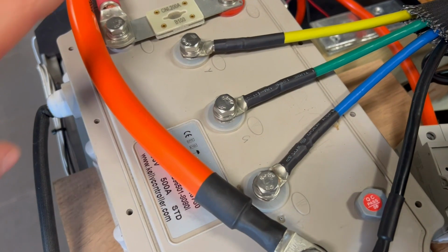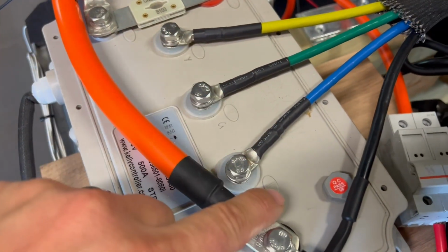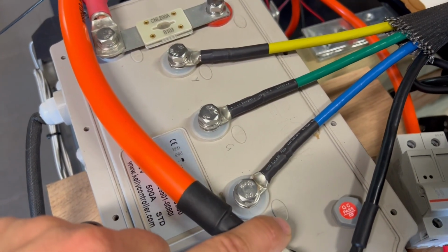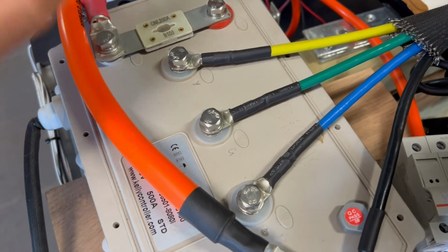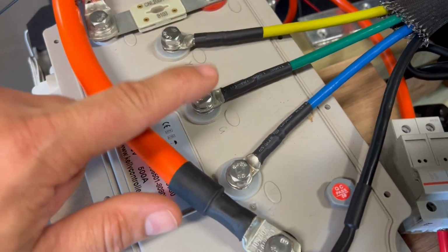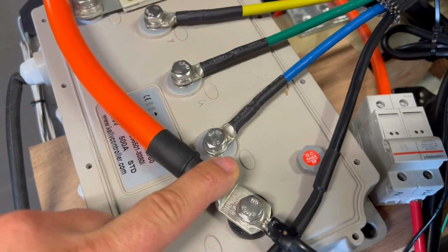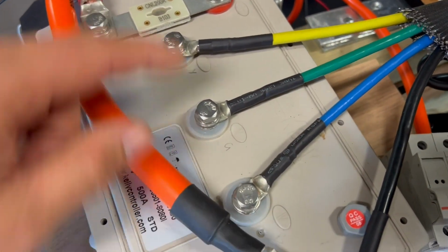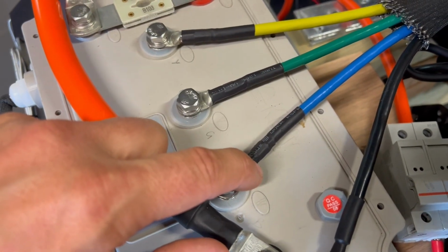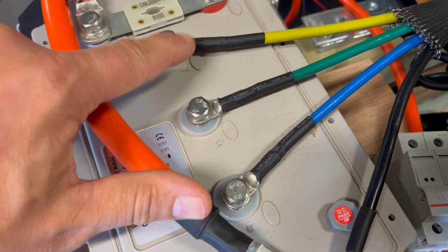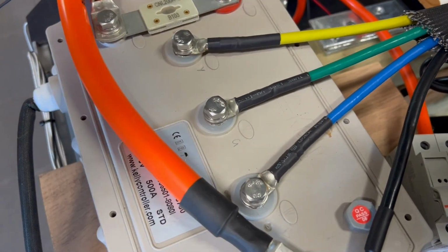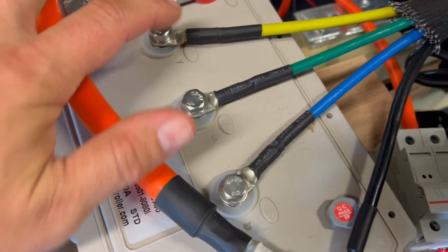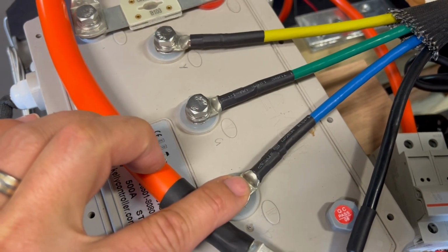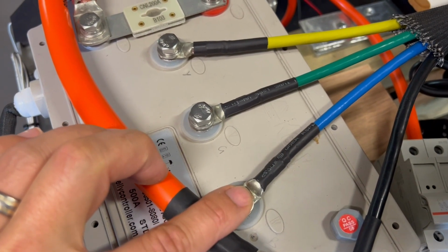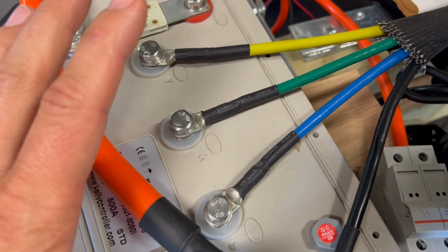On the motor controller, the outputs are marked U, V, and W. So to match these up with the QS motor, U is the yellow lead, V is the green lead, and W is the blue. Now, one last thing, the terminals on the end of the QS motor leads were actually a 6mm terminal, so they had 6mm holes. They just needed to be drilled out to 8mm because these are M8 bolts on the motor controller. So once they're drilled out, they bolt down perfectly fine and they work as they need to.